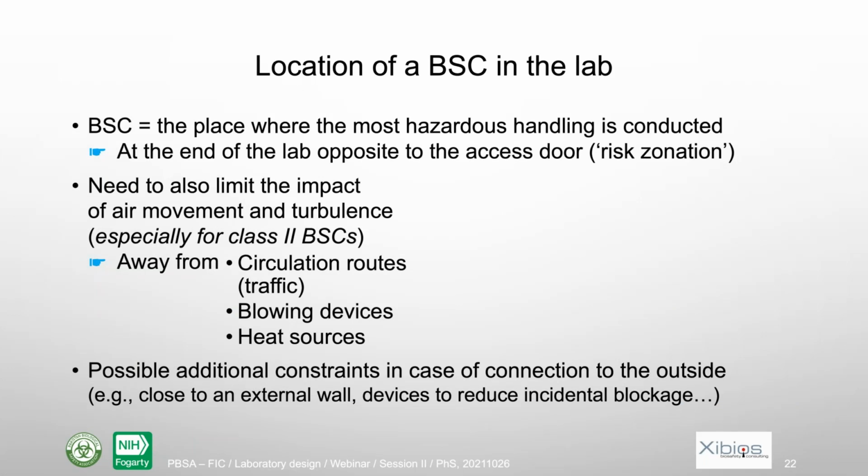I spoke about the location of a biosafety cabinet in the lab. Based on the principle of risk zonation, space zonation, the biosafety cabinet, which is the place where we handle hazardous materials with the risk of aerosols, should be in the high risk area. So it should be at the far end of the lab as opposed to the door.